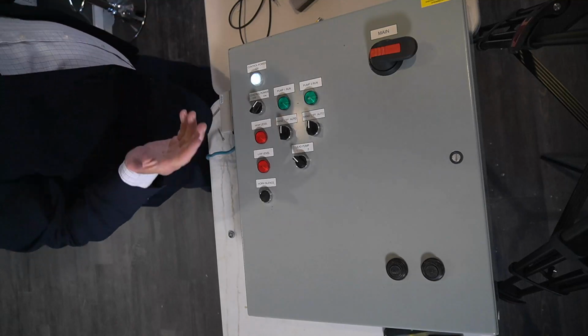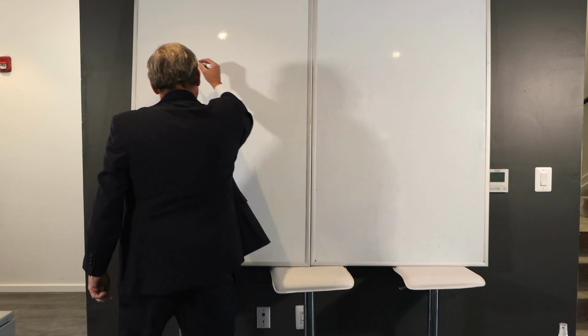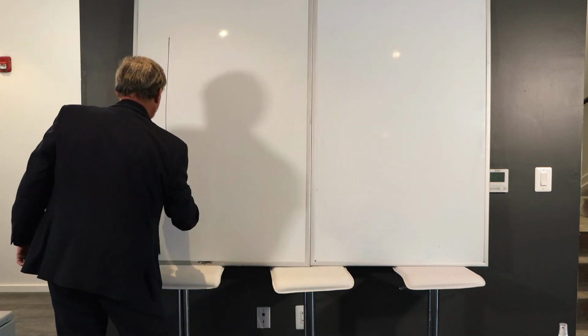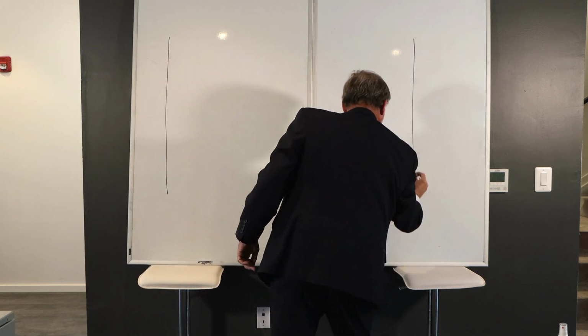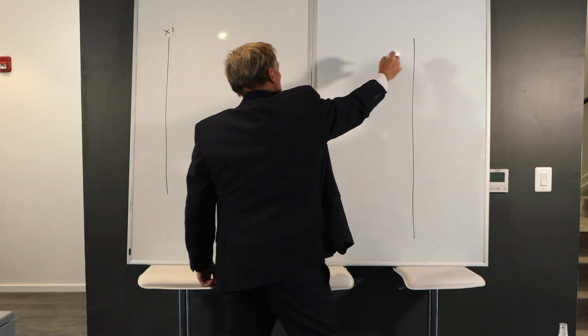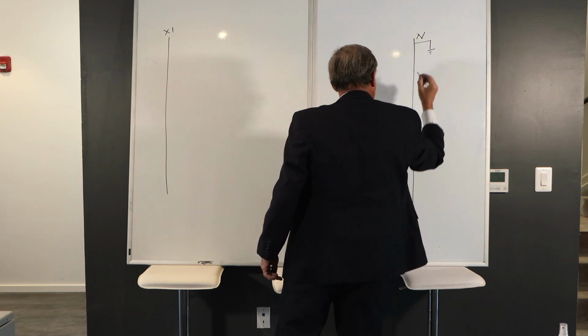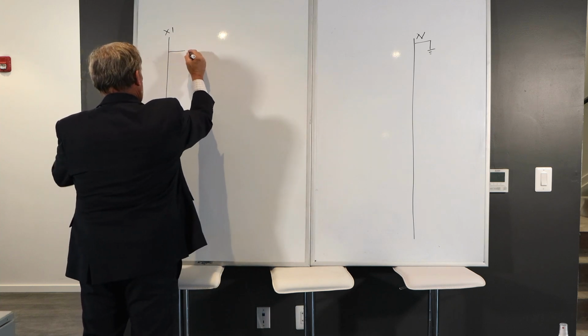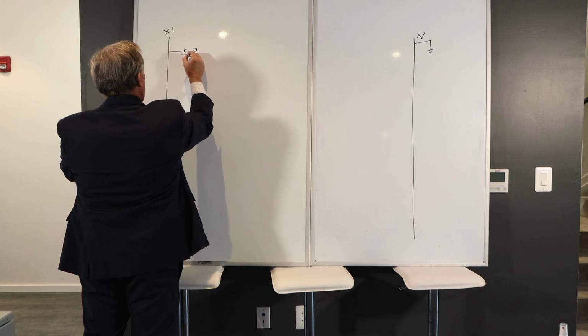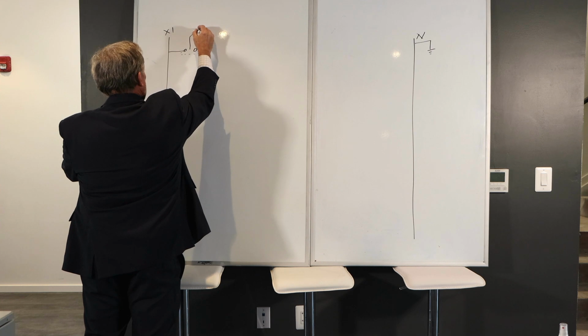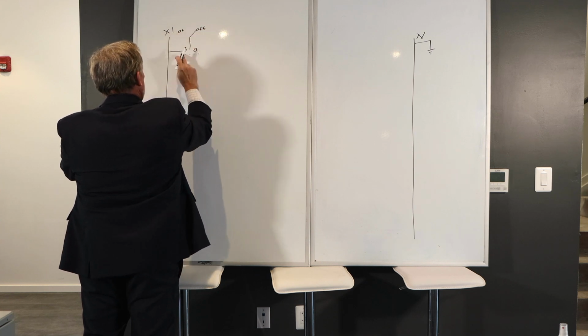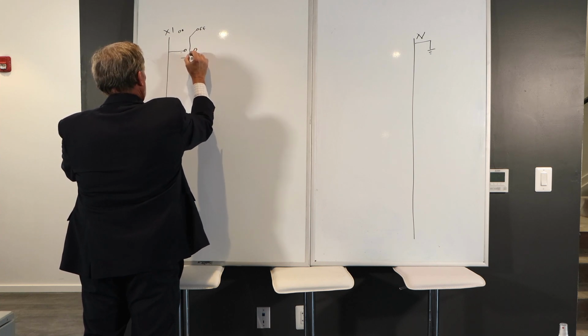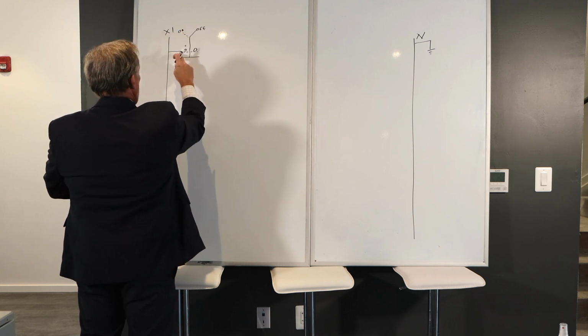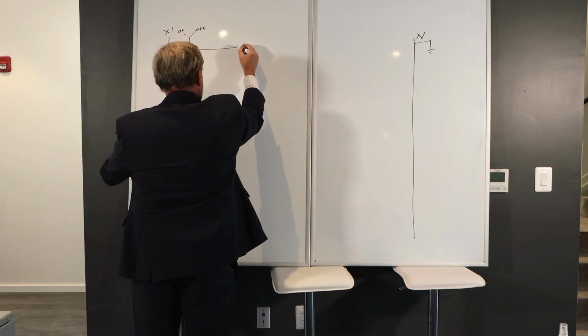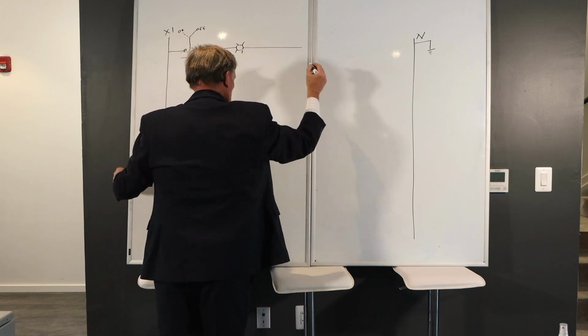First thing we have is a control power on switch. Let's go to a ladder diagram and see what that looks like. Start out, let's do both sides here. This is my X1. This would be my neutral, because remember, we are grounded. Okay, hot wire. I have a selector switch contact. Off position, it's open. I switch to on. We're going to have an indicator light. I want to take this all the way over to our neutral.